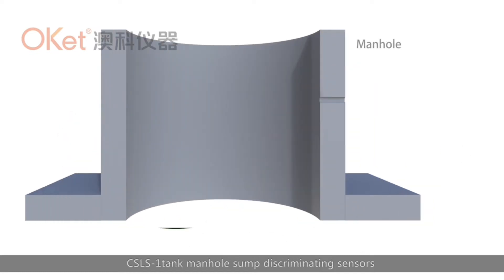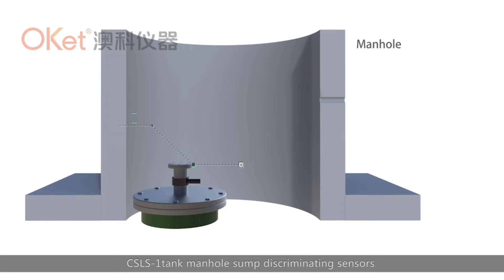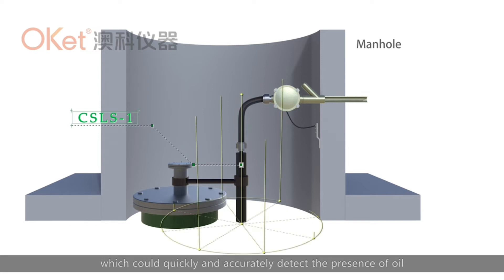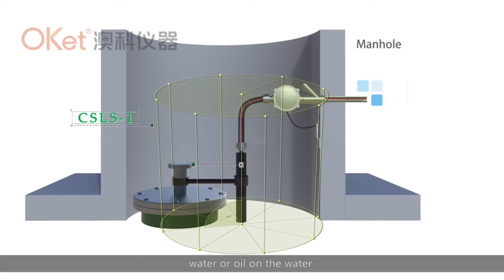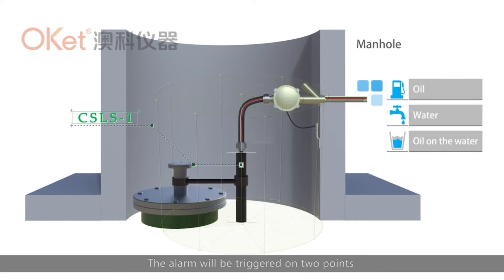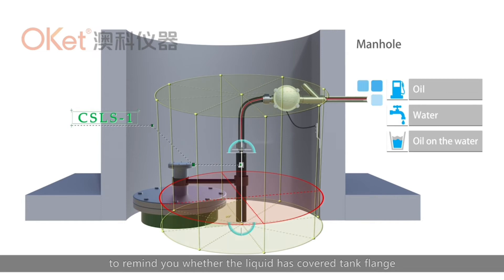The CSLS-1 Tank Manhole Sump Discriminating Sensor is installed at the bottom of the tank manhole sump, which can quickly and accurately detect the presence of oil, water, or oil on water, and differentiate among the three by different alarms. The alarm will be triggered at two points to remind you whether the liquid has covered the tank flange.